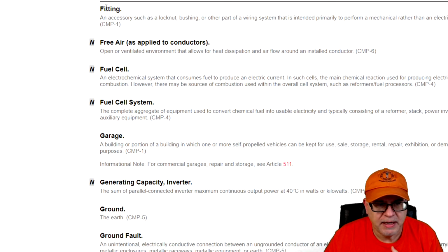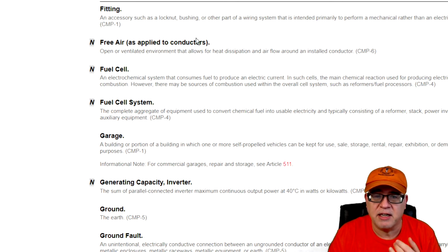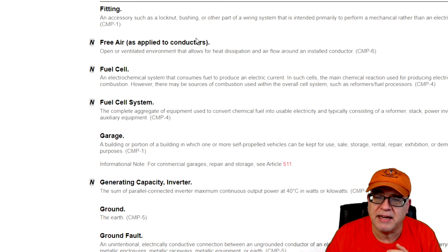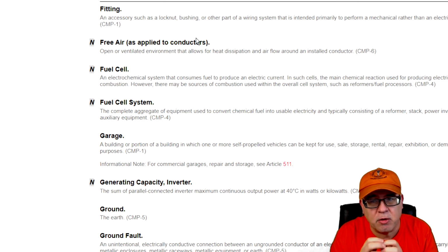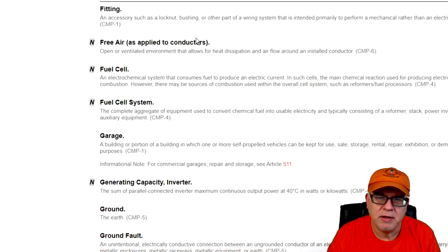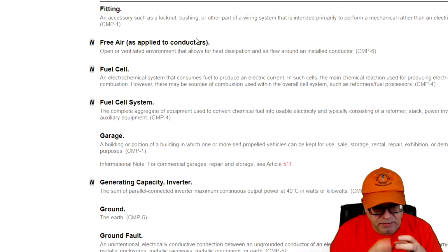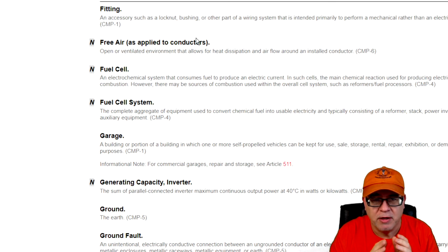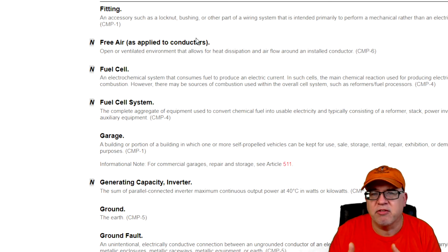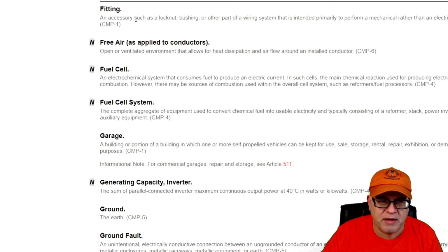Fittings. A fitting is an accessory such as a lock nut, bushing, or other part of the wiring system that is intended primarily to perform a mechanical function rather than an electrical function. So a coupling is a mechanical function. Yes, it does serve an electrical function if it's a raceway that's being used as an equipment grounding conductor, but it's really there mechanically. Lock nuts, for example, are basically a mechanical component, even though in a lot of fittings, it's a very important component to the electrical function of clearing an overcurrent device and things like that. Just remember it says "such as," so it's not all-inclusive when you see this term. It's just giving you some examples.